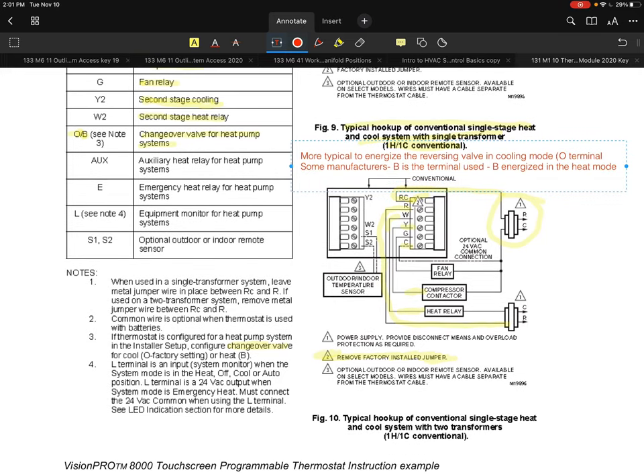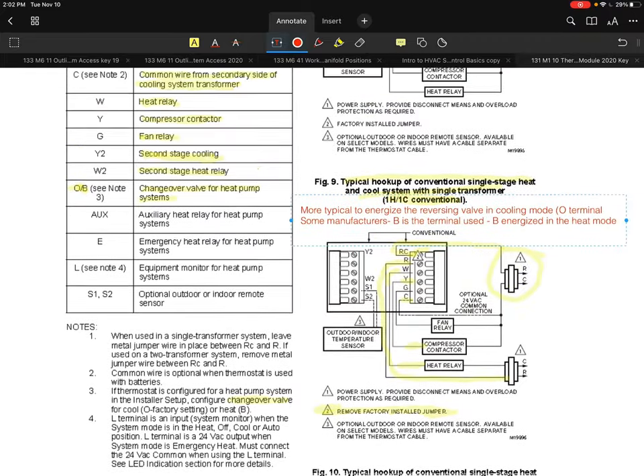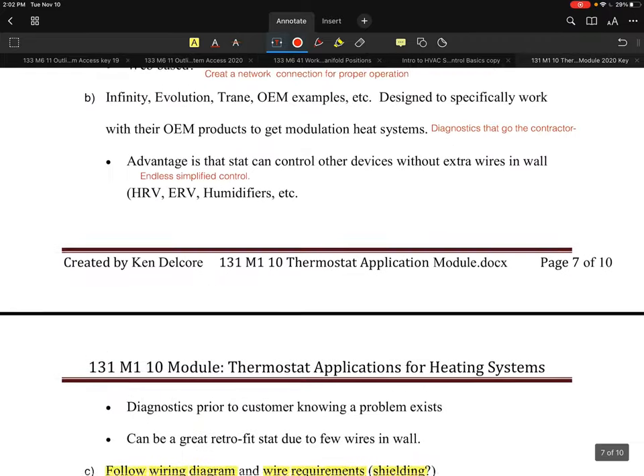Additional heat pump terminals include AUX for an auxiliary heat relay and E for an emergency heat relay — both are heat pump systems only. The L terminal is a 24-volt output used as a fault alarm or emergency heat indicator, energized when the system mode is in emergency heat. S1 and S2 are used for sensor inputs in this example.